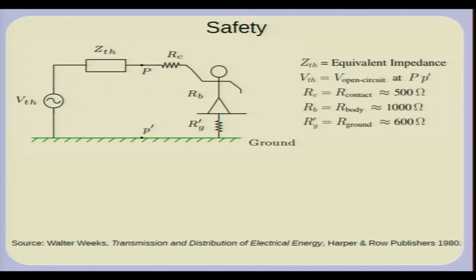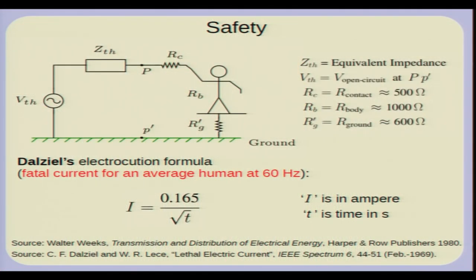When you touch a live point, some current flows through your body, which can affect your muscles and be a safety hazard. This was studied by several engineers in the 1950s and 60s. They found that the fatal current for an average human being at 60 Hz is 0.165 amperes divided by the square root of t, where t is the time in seconds for which the current flows. So for one second, 165 milliamperes can be fatal — an empirical formula reported in several publications.